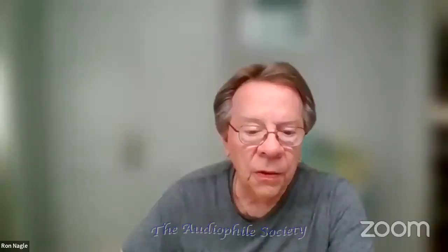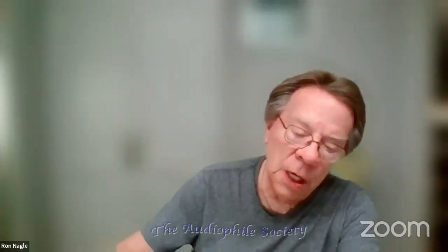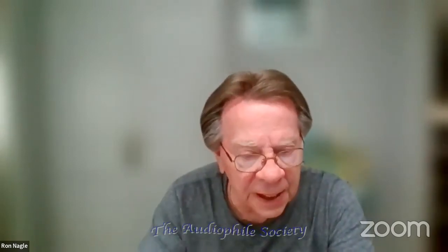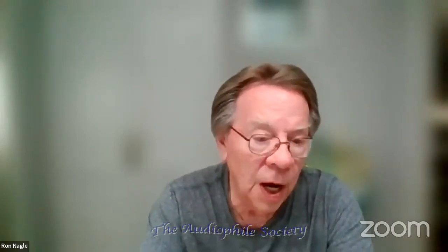Last question, Ron Nagle. You showed us your microscope camera combination, but you didn't exactly tell us what it can correct. Does it have more than one correction ability? Okay, so it is principally designed to measure dynamic stylus rake angle. But particularly the 10 times lens is powerful enough to assess even stylus wear, and the overall general condition of the stylus.